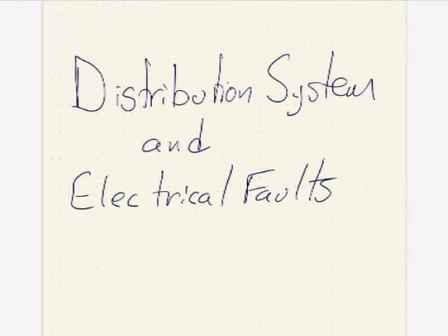Hello everyone. Today we're going to start talking about the electrical distribution system and faults. A fault occurs when you have a failure in the equipment on your electrical system, and it allows the electrical energy to flow somewhere where it shouldn't. This could be phase to phase, it could be directly phase to ground through a conductor, it could be a result of lines laying on the ground. And so an electrical fault is what happens when you get any flow of electricity through an unintended path.